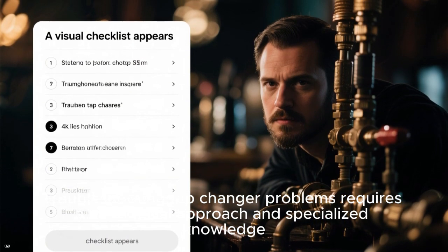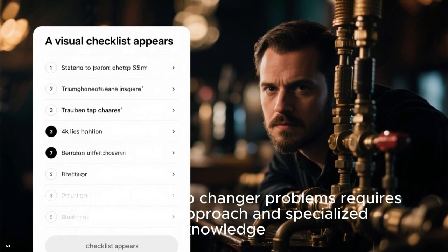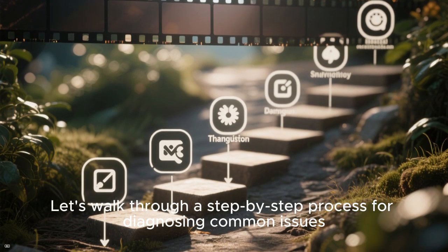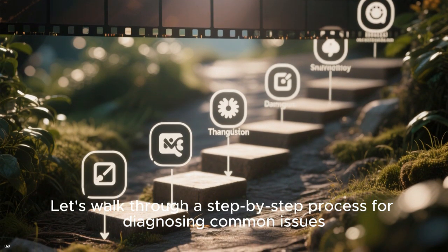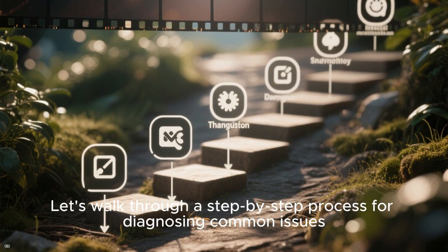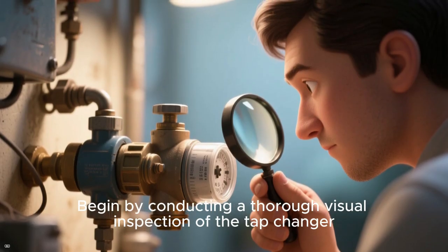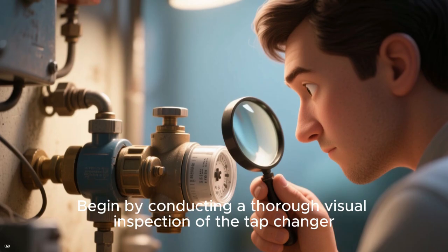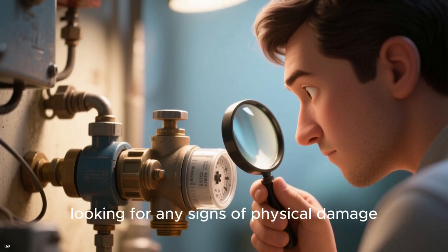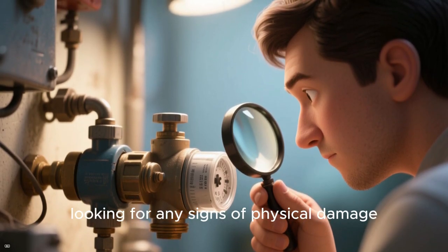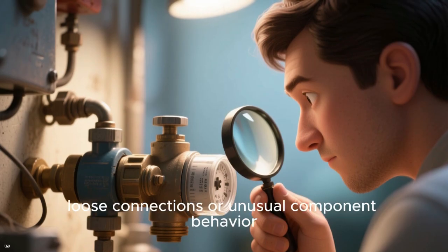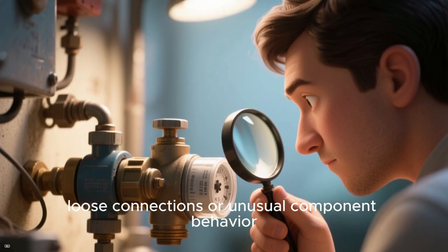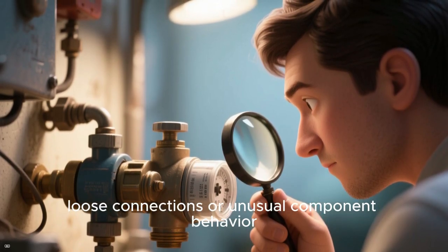Troubleshooting tap changer problems requires a methodical approach and specialized knowledge. Let's walk through a step-by-step process for diagnosing common issues. Begin by conducting a thorough visual inspection of the tap changer, looking for any signs of physical damage, loose connections, or unusual component behavior.